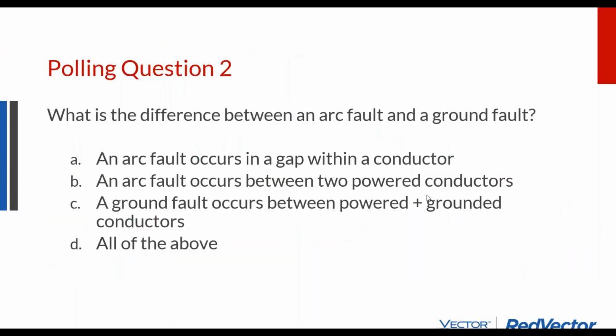Yeah, so again, a common one that I have found in the solar industry is these little black connectors. Not just if that ending is not connected with a click, but if these connectors at the bottom are not fully tightened up to secure that cord well within the connector head, that can cause an arc fault. If everything else is perfect on day one, you start the system up and one of the circuits is not checked in, it's probably in one of these connectors. And if the circuit did check in and then all of a sudden a day later it doesn't check in, it's probably an arc fault in one of the connectors that is field made between the array and the inverter.